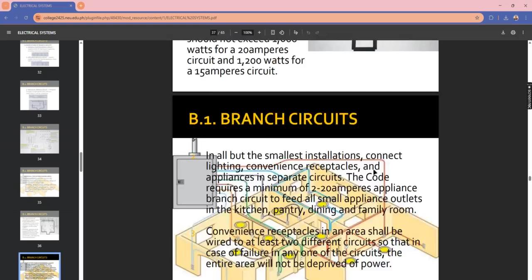Okay, there's a note here: good practice suggests that the load should not exceed 1,600 watts for a 20 ampere circuit, and 1,200 watts for a 15 ampere circuit. So when we compute our schedule of loads...